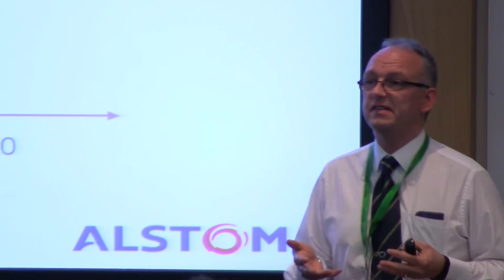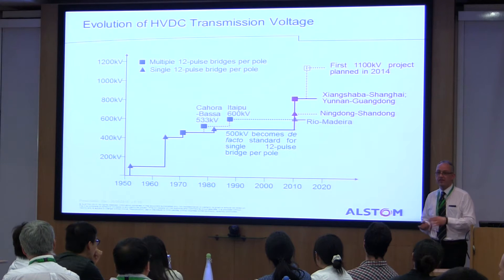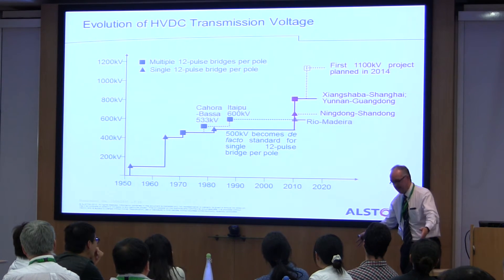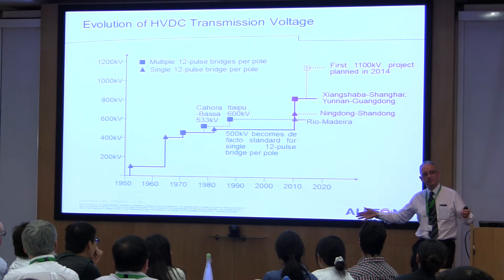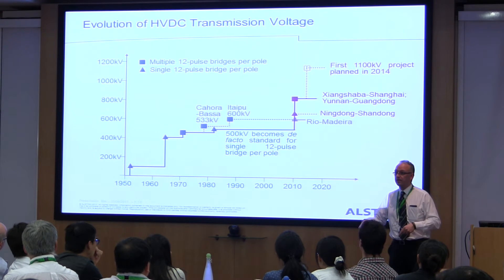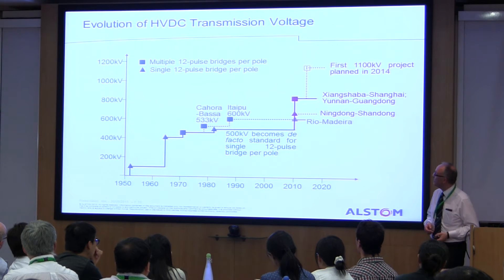When you're designing an HVDC scheme, one of the biggest challenges is getting the transformer to site — that's the biggest single item. Everything else is shipped easily; valves come in a packing case and you assemble them on site. The transformer is the one big thing you have to take to site, and it can very often be the thing that influences your design. If there's a bridge you've got to go under, that will limit the height of the transformer and mean you have to have a higher leakage reactance than you'd ideally like. If you've got to go over the bridge, you've got to get the weight down. At 1100 kV, they're talking about building the valve hall first and using it as an assembly plant for the transformers — shipping them in bits, assembling on site, and then populating the valve hall with the valves.